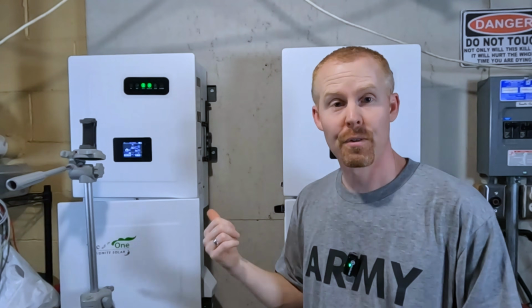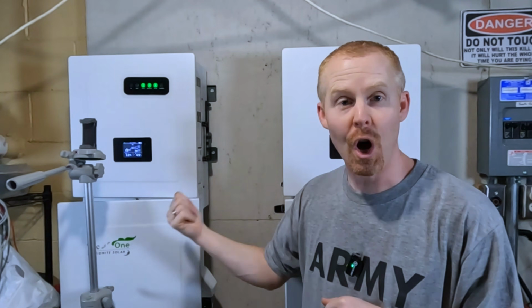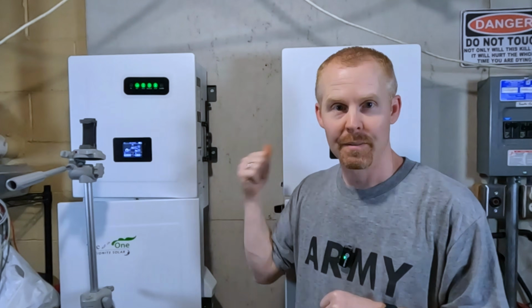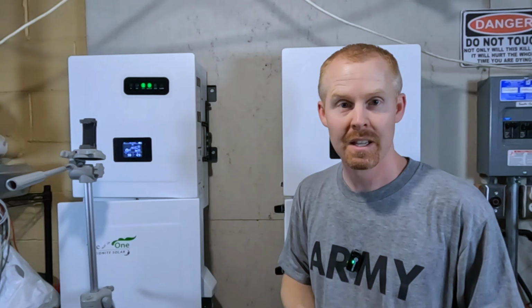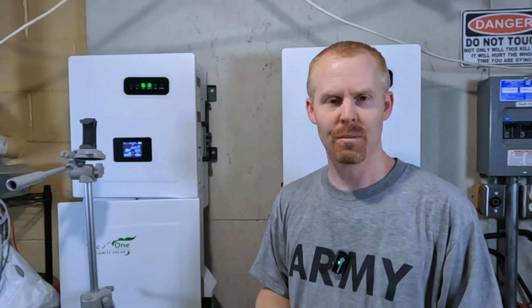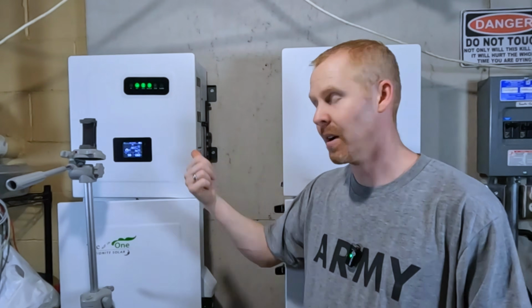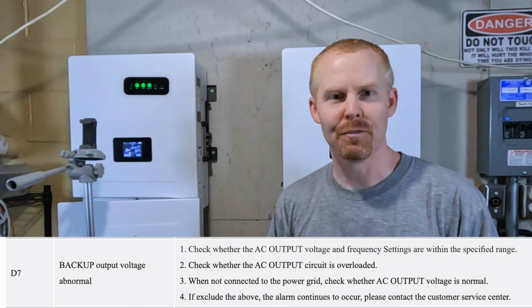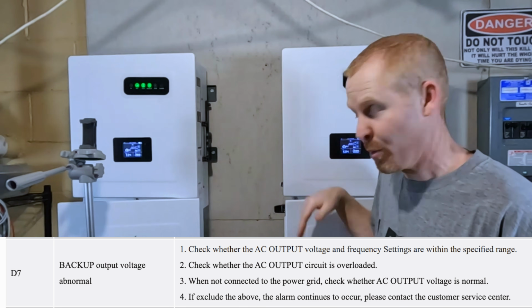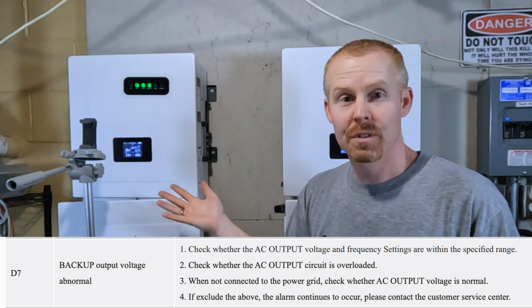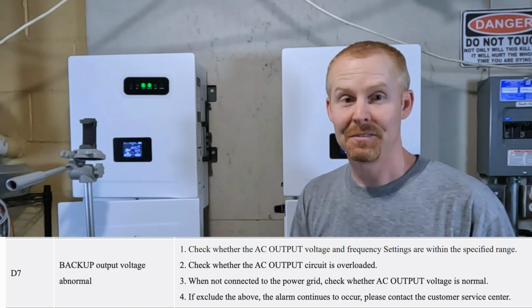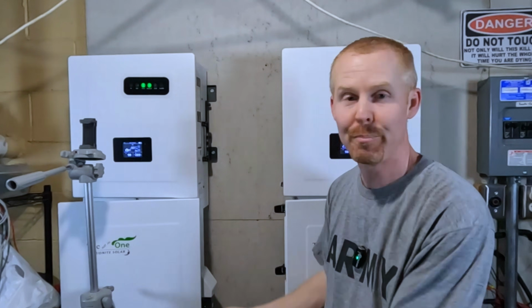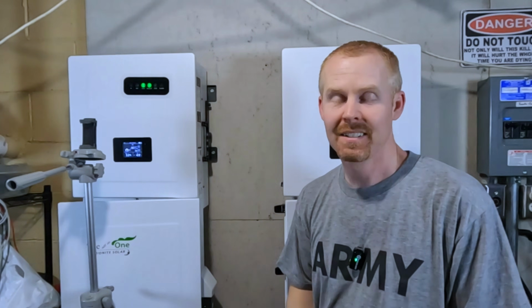And actually, I've gone through unparalleling these before and forgot to turn off the breaker on the secondary inverter, turned the main inverter back on so that it was supplying power to the house, and then I noticed this weird error on the slave inverter. I'm like, well, what's going on? They're not stacked anymore, so why am I getting the error on this inverter? And it's abnormal AC output voltage. Oops. This inverter was backfeeding to the output on this breaker, and all it did was throw a warning. It didn't cook it, didn't fry it, nothing. So that was kind of sweet to see, because I thought, oh no, I ruined something because I backfed power to the output breaker. But it's like, hey, hello, over here, something's not right. And it warned me, and I turned the breaker off and the warning went away.